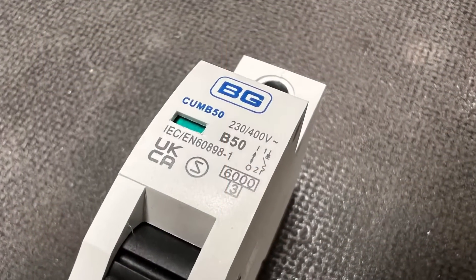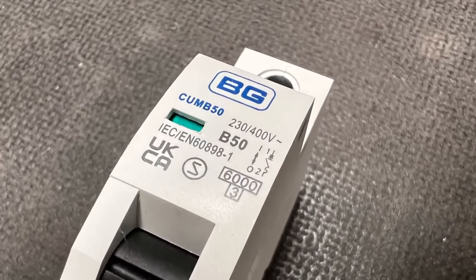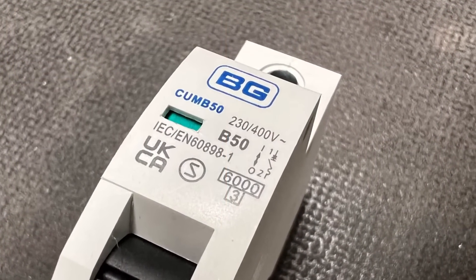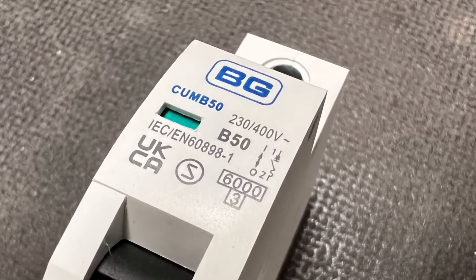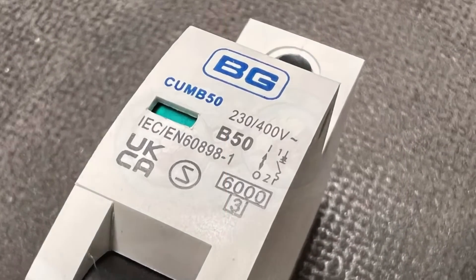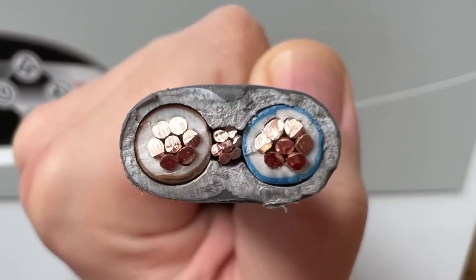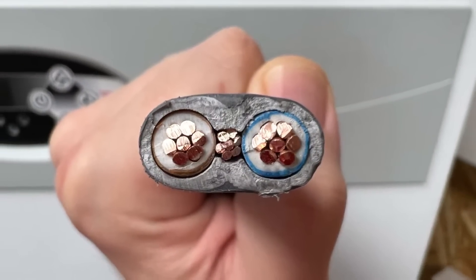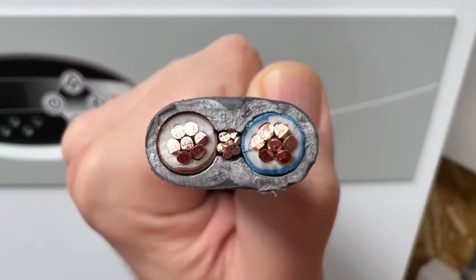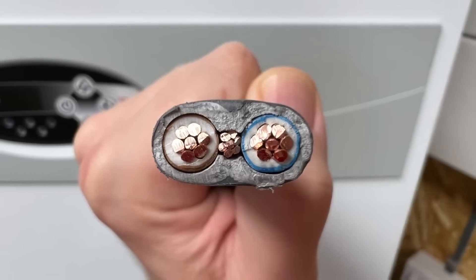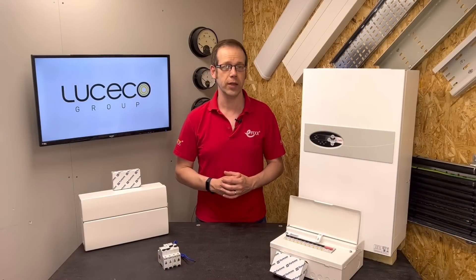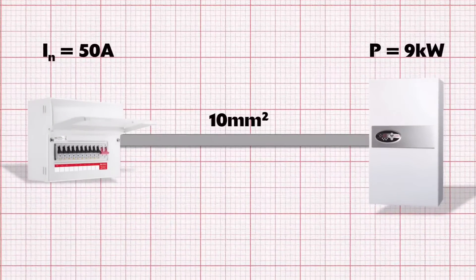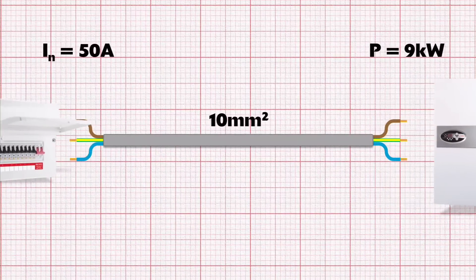We know that the MCB will allow the current to pass through itself without tripping under normal operating circumstances, and we know that the cable will be able to take that amount of current. But there are still some checks to be made on the cable we've selected to make sure that the load will operate correctly under normal running conditions. The first of these is the volt drop.